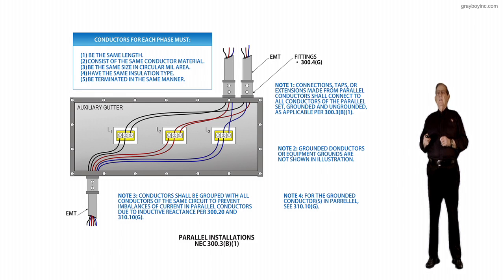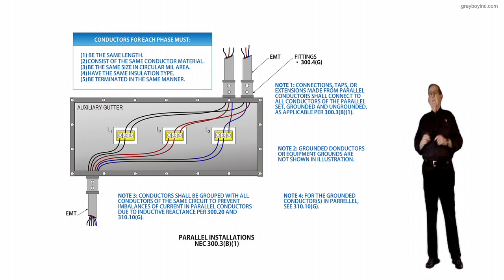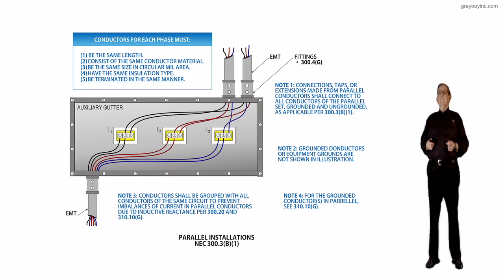Note one states that connections, taps, or extensions made from a parallel set of conductors shall be connected to all conductors of the parallel set, grounded and ungrounded, as applicable per 300.3B1.